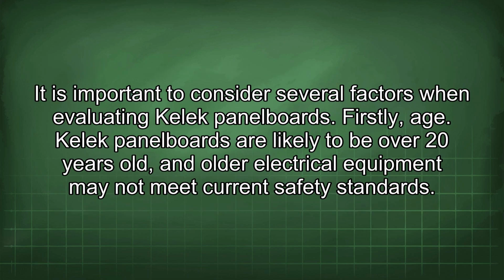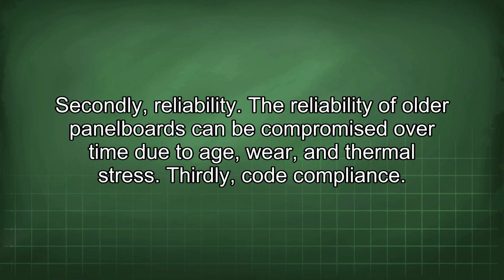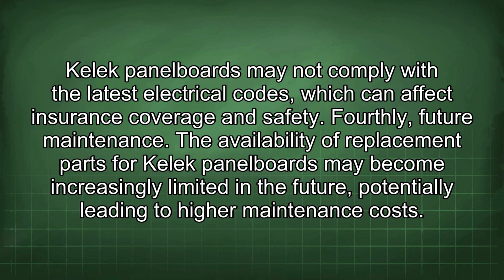It is important to consider several factors when evaluating Kelek panel boards. Firstly, age. Kelek panel boards are likely to be over 20 years old, and older electrical equipment may not meet current safety standards. Secondly, reliability. The reliability of older panel boards can be compromised over time due to age, wear, and thermal stress. Thirdly, code compliance. Kelek panel boards may not comply with the latest electrical codes, which can affect insurance coverage and safety. Fourthly, future maintenance. The availability of replacement parts for Kelek panel boards may become increasingly limited in the future, potentially leading to higher maintenance costs.